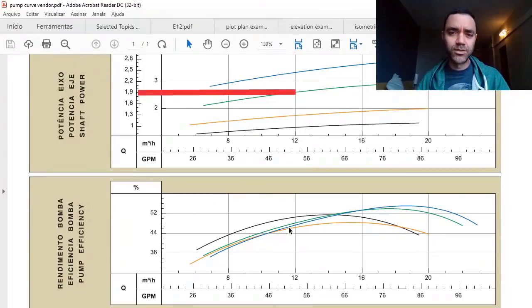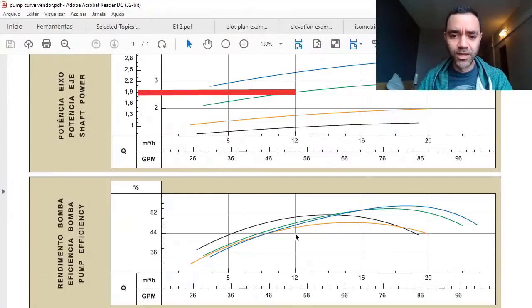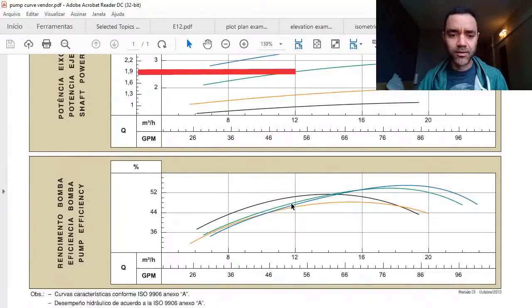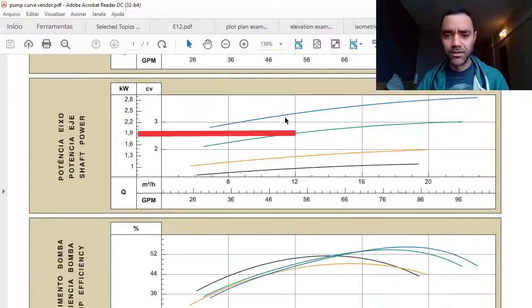When we talk about smaller pumps, sometimes the suppliers add the pump efficiency already considering the motor efficiency. If we use this information and feed it to Aspen HYSYS, you're able to get the power based on this information of head, flow, and efficiency, and verify that everything is talking to each other.